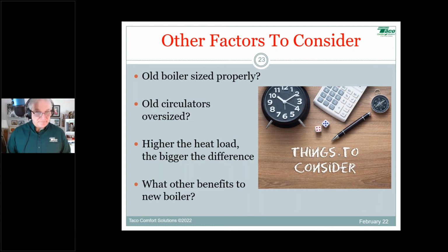There are plenty of people who've installed that circulator as the boiler circulator for a ModCon boiler, set up to give you the Delta T across the heat exchanger you've designed for, and that's a terrific application. Some manufacturers are cool with it, some aren't, so always check with your manufacturer. In the big picture, learn how to properly size your boiler circulator, bigger's not always better, bigger's not always necessary.